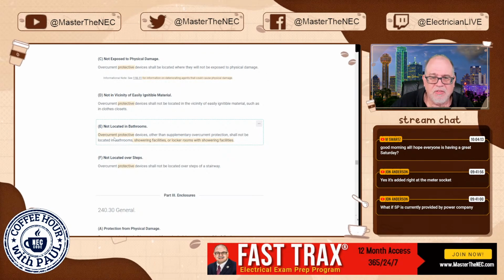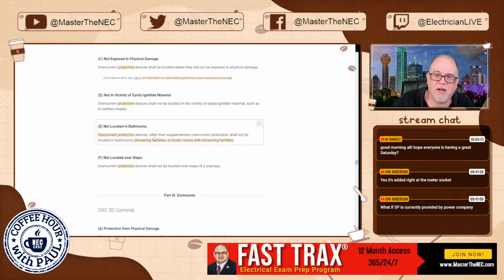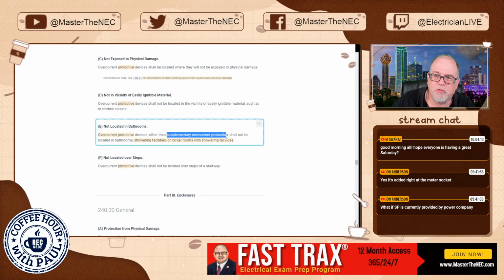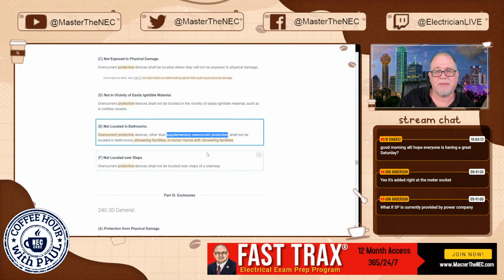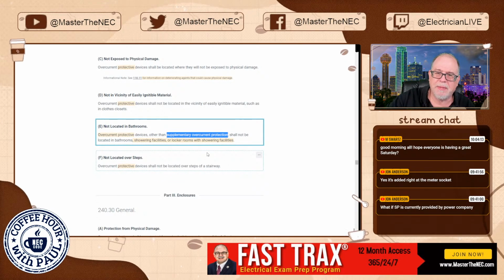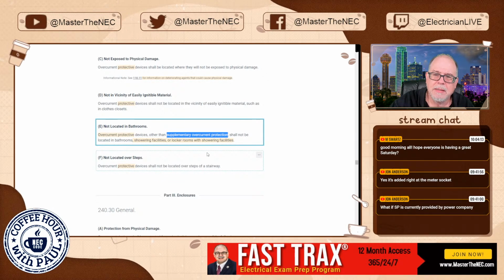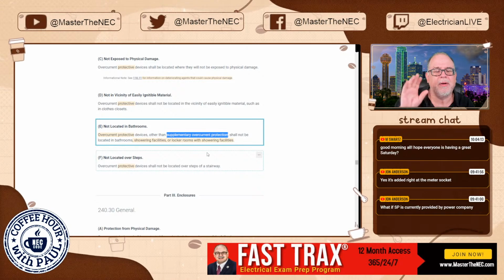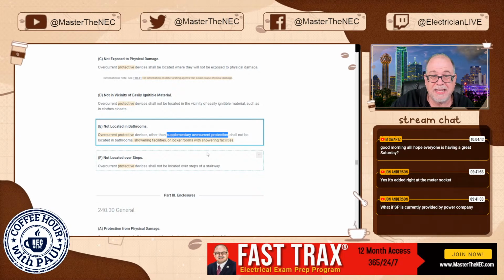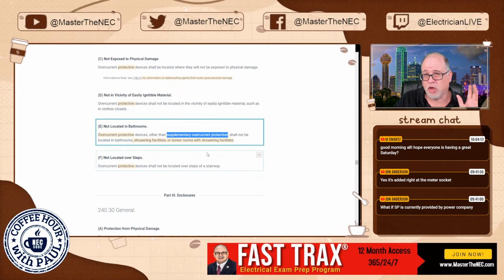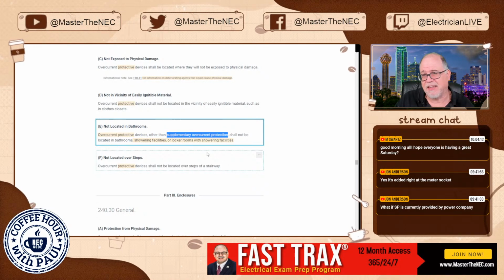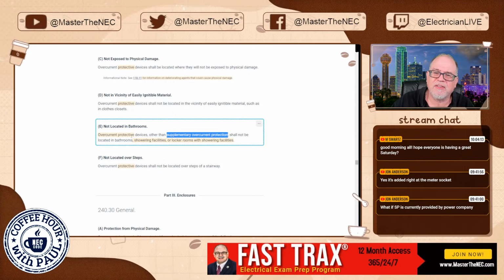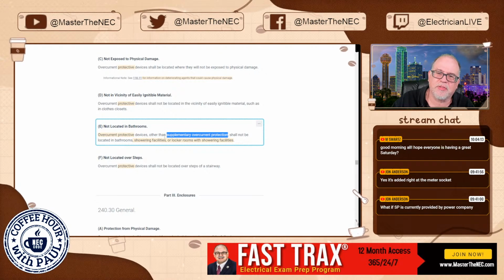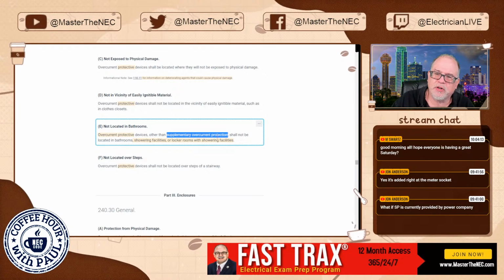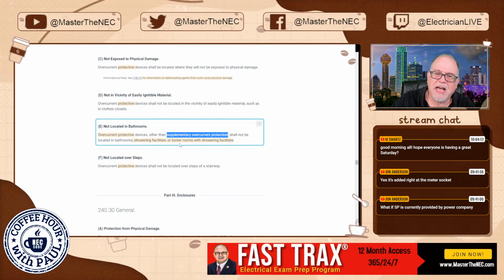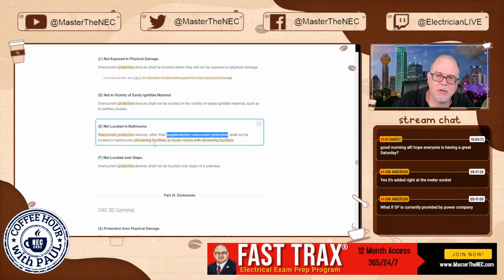And here's what it says. Overcurrent protective devices other than supplementary overcurrent protection. So you could have overcurrent protection for a piece of equipment that's located in that bathroom, but that is supplemental to the piece of equipment. It's not the main overcurrent protection for the branch circuit, let's say, that might be going there, right? So it says overcurrent protected devices other than supplementary overcurrent protection shall not be located in bathrooms.